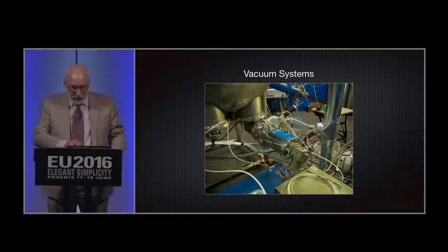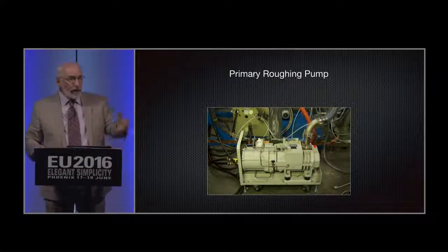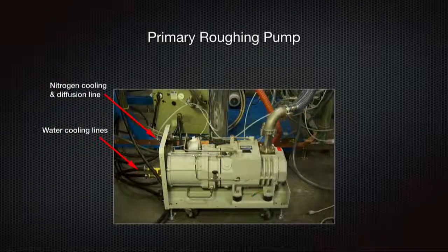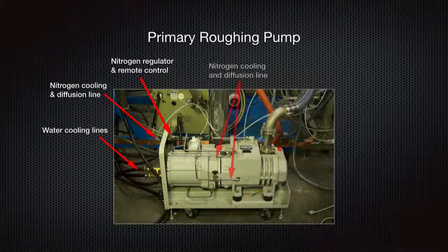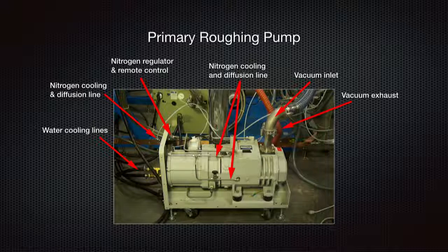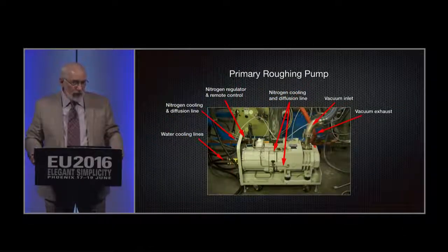And I think that's it. So it's complex. This is the main vacuum pump, and it sucks, big time. It will take the chamber down to 10 minus 3 or 2, 3? 10 minus 2 in about 15 minutes. Okay? If anybody knows anything about vacuum pumps, this is from Oerlikon.